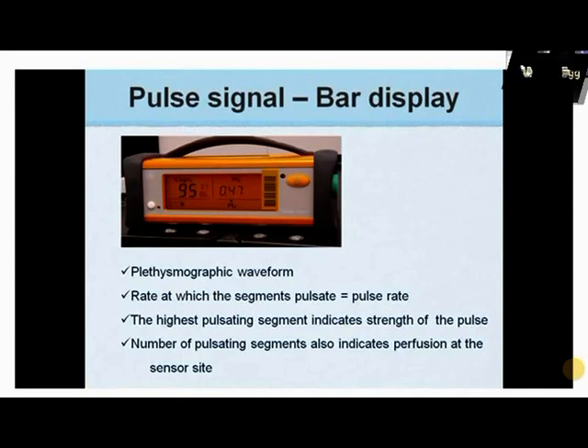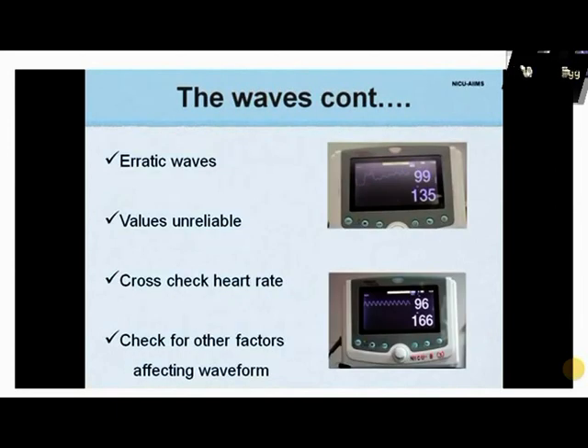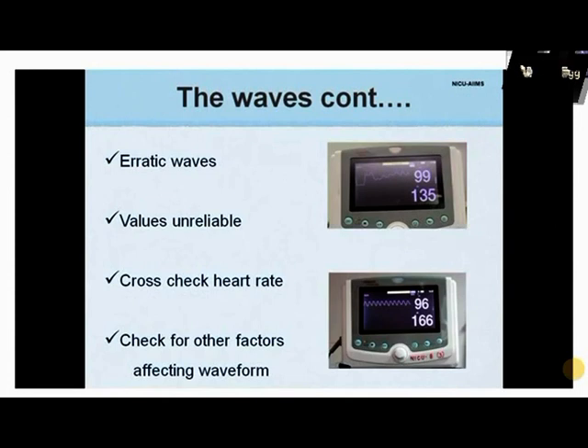If the bar display is less than 50%, it indicates poor quality signals. If the waves are not uniform, the values displayed are likely to be erroneous. A practical approach is to cross-check the heart rate of the baby with the displayed value — they should match within 10% of each other. The causes of non-uniform waves should be corrected before attributing any significance to the displayed values.